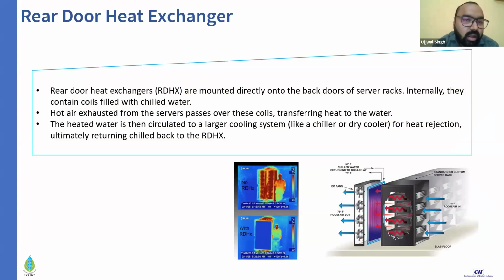This is what we've done now: instead of placing the cooling system adjacent to the server, we place it on the back side of the server. This technology is called the rear door heat exchanger system. These images were taken from one of the data centers we visited in Bangalore, India. Without a rear door heat exchanger, hot air comes out and needs to be collected and cooled down elsewhere. But with a rear door heat exchanger, the air is cooled right there and is ready to be absorbed by the front side of the rack from that point onward.